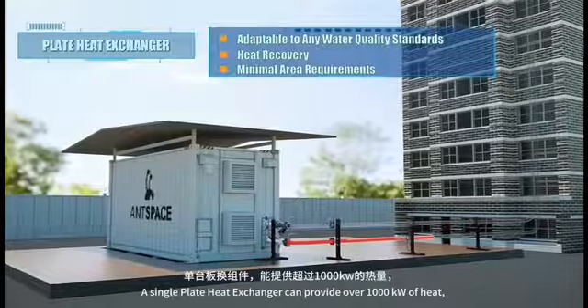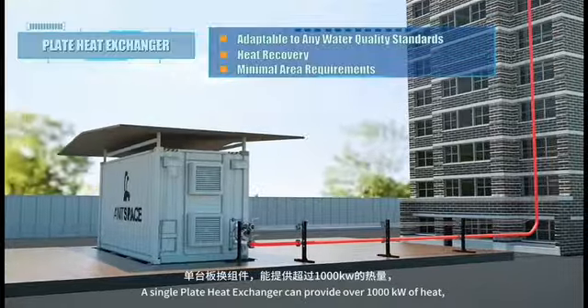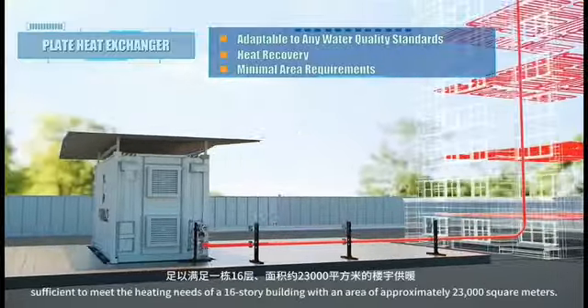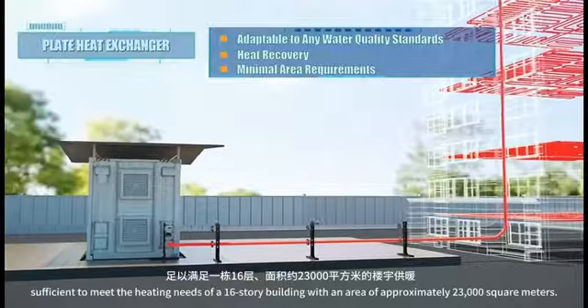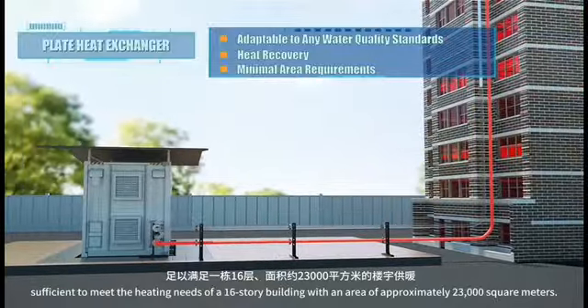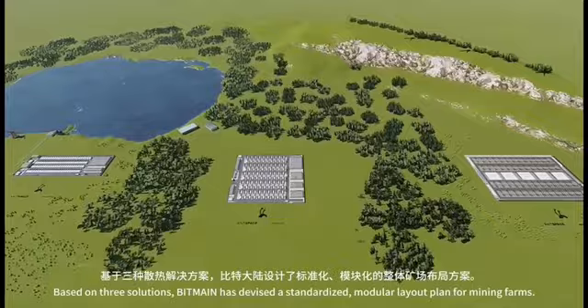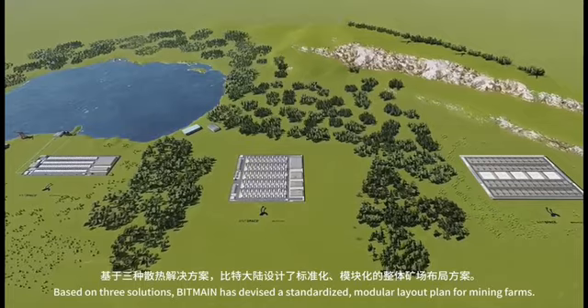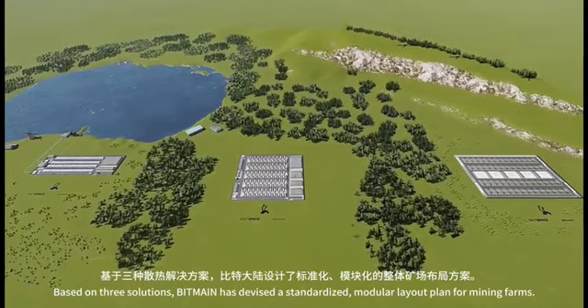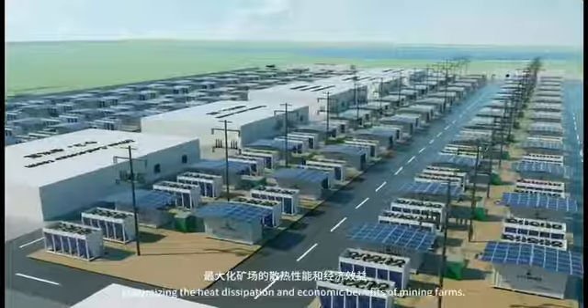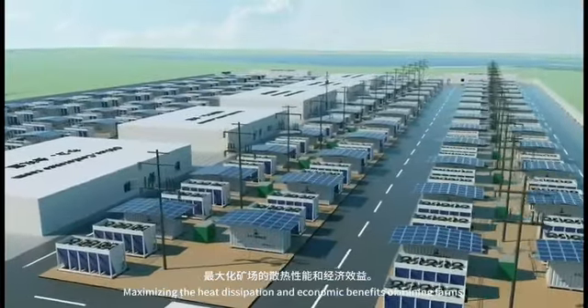A single plate heat exchanger can provide over 1,000 kilowatts of heat, sufficient to meet the heating needs of a 16-story building with an area of approximately 23,000 square meters. Based on the 3 solutions, Bitmain has devised a standardized, modular layout plan for mining farms, maximizing the heat dissipation and economic benefits of mining farms.